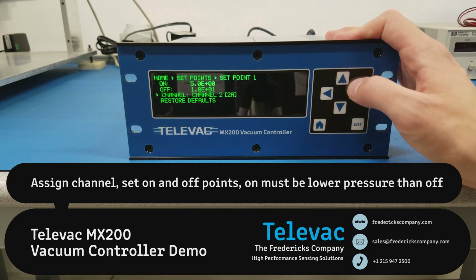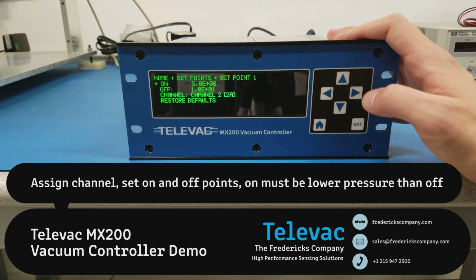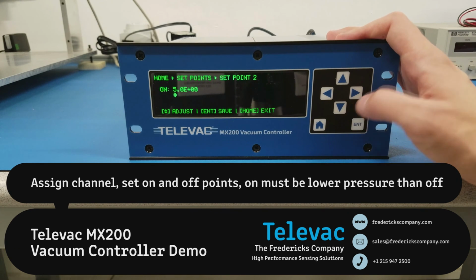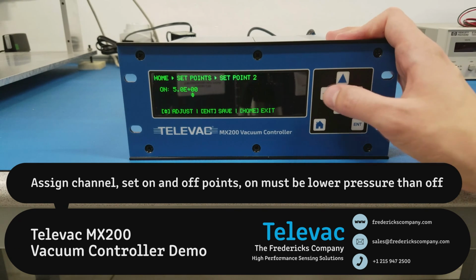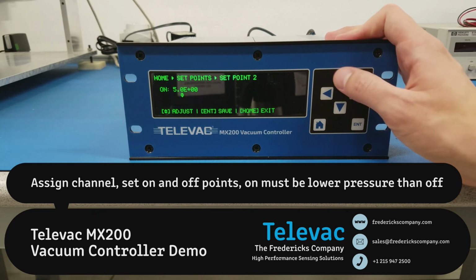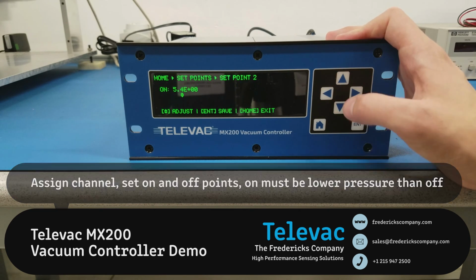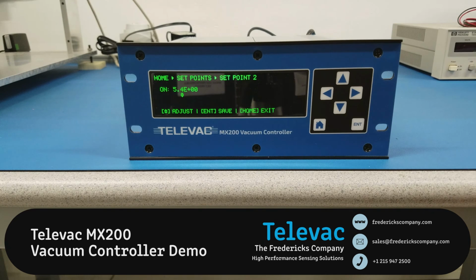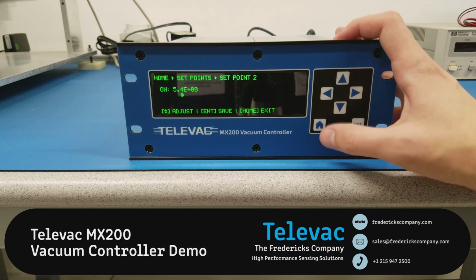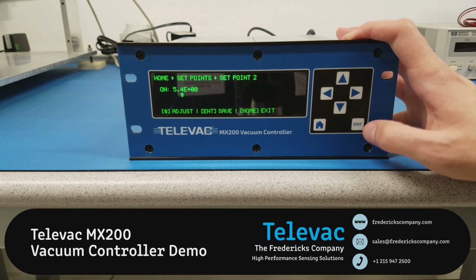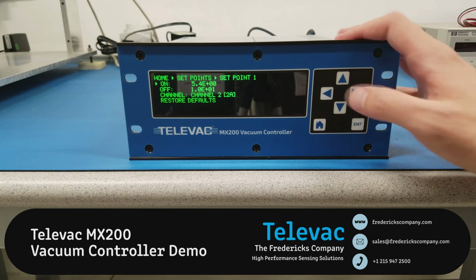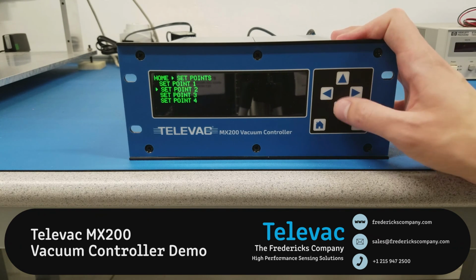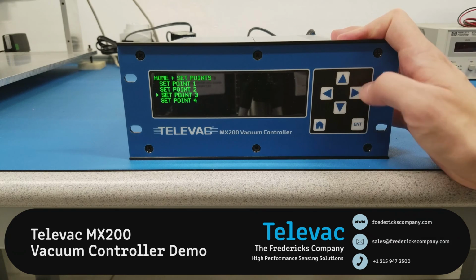You can back out. And then you can go into the on and off values for the set point. You can use the left and right keys to scroll between digits, and then the up and down arrows to adjust the value. If you want to exit without saving, you can hit the home key, or if you'd like to save the value, press enter. And this can be done for all of the set points individually.